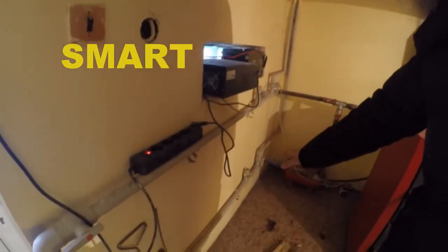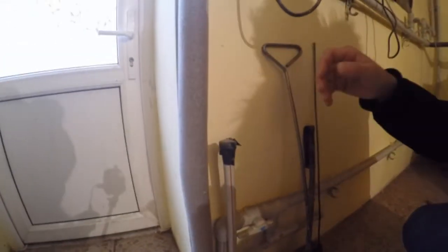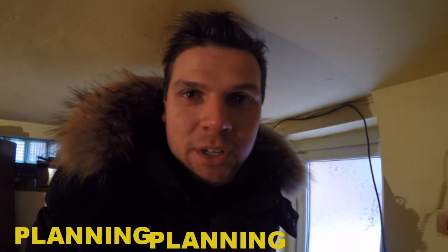What about hot water? Right now they have a tankless water system, but they also want to get off the gas grid with that appliance. So what they've done is they've planned for the future. He's added a valve to the supply and a valve to the return that will be sending your boiler water through a heat exchanger. Over here we have two half inch pipes — your domestic hot water and your cold water supply. I recommend planning ahead. It's always a smart idea. Even if you're not going to use it this year or next year, at least you have it. Ask your technician, build it, leave it — in the future we will finish it. At least it's there. Come on, let's check out the other boiler room.